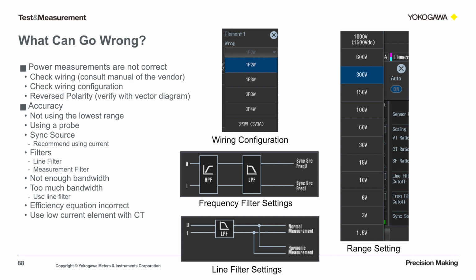Your efficiency measurement could be incorrect within that screen I showed before. Make sure that you have the right numerator and denominator. And you might not be using the lowest current element with your CT, meaning if you're using a current transformer, it outputs 1 amp or 2 amps. So you'd want a current element that matches, not up to 50 amps, because you'd be giving up accuracy.